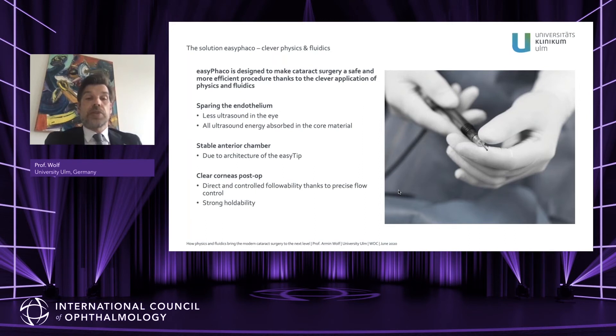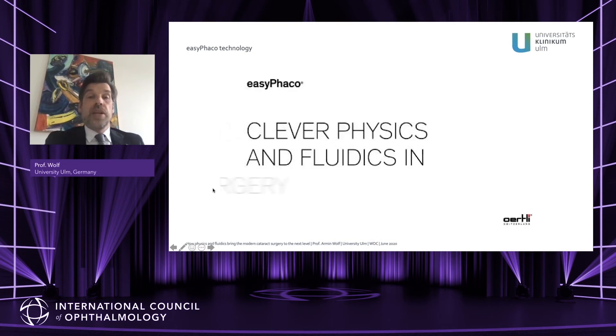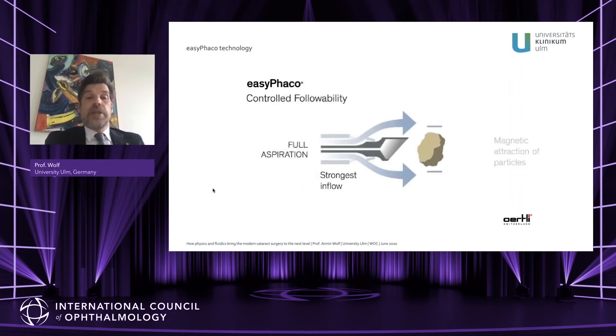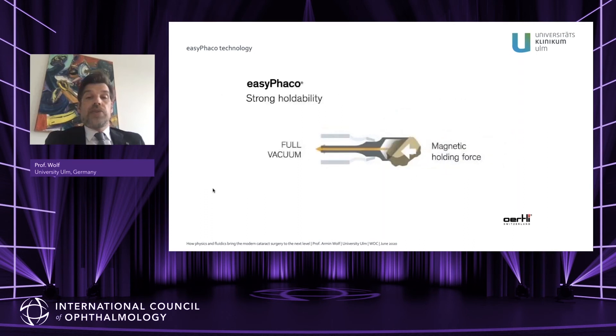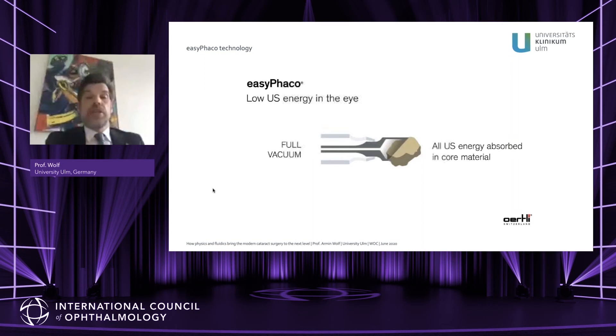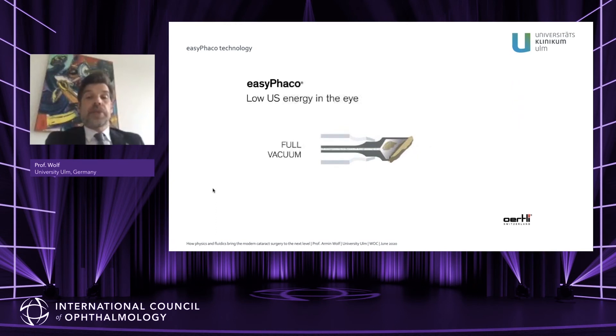Altogether, this allows you to have clear corneas postoperatively, with directly controlled followability thanks to precise flow control and a very strong holdability, avoiding surging fragments. All nuclei can be treated with easyPhaco. By using a special design tip, there is a magnetic holding force of the fragment to the area of ultrasound application, and all the ultrasound energy is absorbed in the core material of the fragment. This allows you to perfectly couple hard as well as soft materials, with fine emulsification and no clogging of the aspiration.